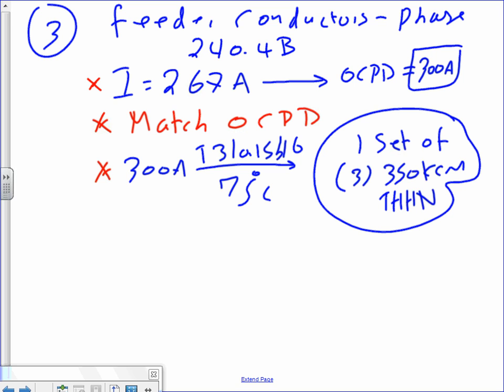Let me know when you guys are done. Can you guys highlight match overcurrent protection device for the feeder? OC, overcurrent protection device, OCPD. What's under the 300 there? 75 degrees. I always write 75-degree column, guys, to emphasize which column you always go to. 75. So when you go to the table, you can see where I put my arrow. Right underneath it, I put a column. If you say you always go to 75, when you're in the industry, you're right 95% of the time.